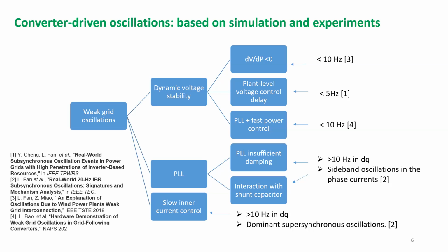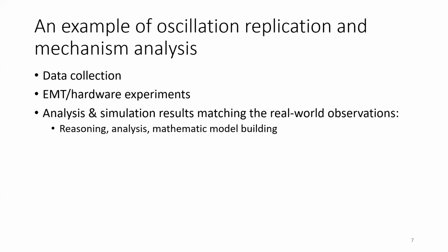It can also be because of the PLL and its interaction with the fast power control. At the PLL level, it can be insufficient PLL damping because you put a lot of filter to filter out the negative sequence, or because of interaction with the shunt capacitor. And if the inner current control is not designed ideally, you can again see something happening. So it's not that simple that we can just say what this is. This is based on simulation. Now, the most difficult part in real world dynamic analysis, besides data collecting and having EMT, is the matching part, because you really cannot directly connect the dots easily. So I emphasize that this is about reasoning, analysis, mathematical model building, and iteration. It can take years of thinking to finally figure out what is happening.